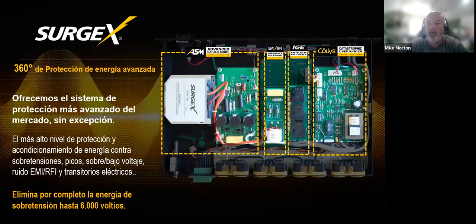The second problem, called overvoltage, is a significant issue. It's because voltage will rise but sustain itself at that level for a period of milliseconds. Milliseconds in the world of electronics is like a year to us. And what happens is when you have that overvoltage, or voltage that is too high for a period of time, it will cause heat in the power supply of the device that's using it. That power supply does not have the ability to dissipate that heat anywhere other than the board, the semiconductor board. And as we all know, semiconductors do not like heat. So when that heat rises, or if it's in the case of an undervoltage where it's down too low, the power supply is starving for power. Again, it generates heat in that power supply. That power supply can be damaged, but just as importantly, that heat can be transferred to the semiconductors on the board and cause damage to the board.